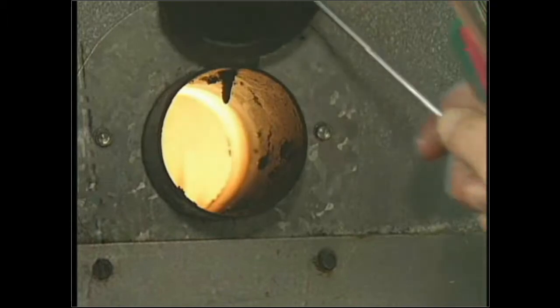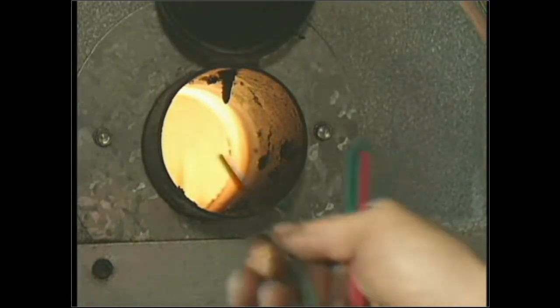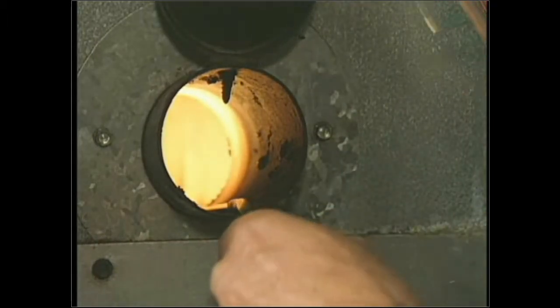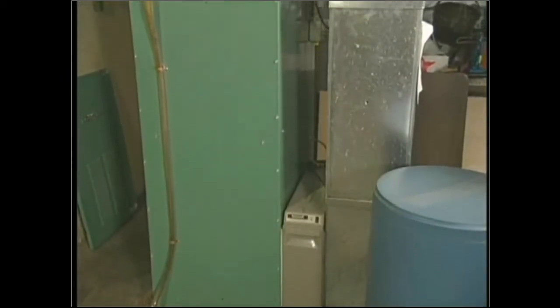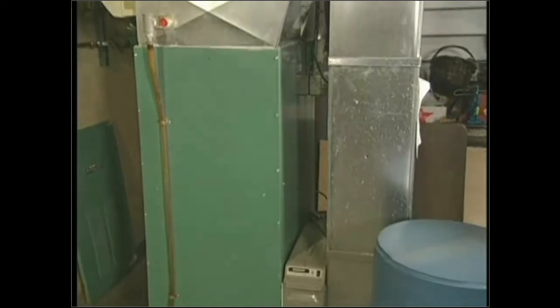They run anywhere from 350 to 550 degrees. So that's hotter air, so it's more likely, if it's cracked, to have discoloration on the paint. Okay, so do a thorough inspection of the box itself. Pay close attention to any discoloration that might occur there.